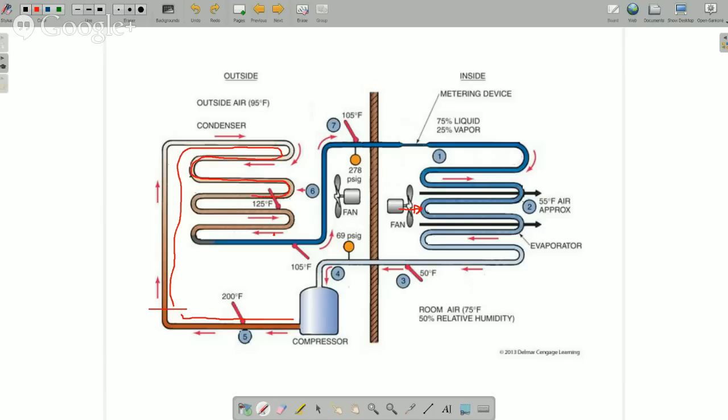And what's going to happen is it's going to continue to flow through this condenser, and because we have less refrigerant, it doesn't back up like it should in the condenser. It continues to travel down here, and then it gets to a point where it does back up. So this refrigerant doesn't spend a lot of time between this point right here and this point right here to pick up subcooling, and it blows through the condenser faster than it should and doesn't back up until it hits right here.